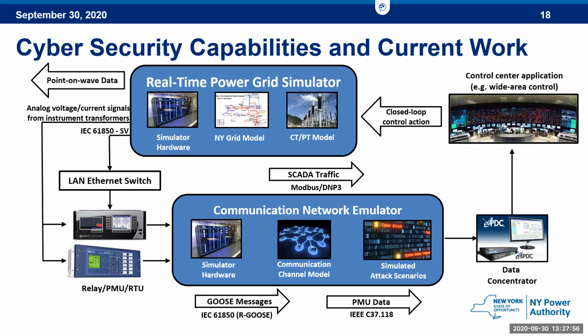This traffic can then be exported to a concentrator. In this instance, I have a phasor data concentrator, but it could be any concentrator depending on the traffic being implemented. The idea is that this data is then used as input to a wide area control scheme, or a local control scheme if remote data is needed for it, and this, in a closed loop setting, controls the grid.